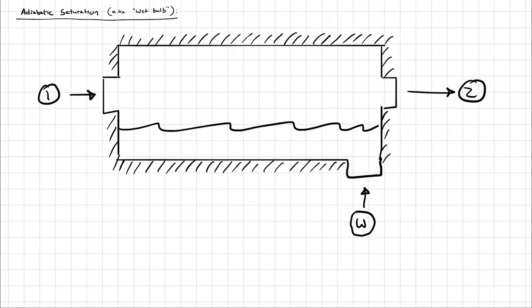One of the oldest and most accurate ways to measure humidity is with two thermometers. One thermometer measures the regular temperature. On the other thermometer, you wrap it in a wicking that holds water and allow as much water as can evaporate to evaporate. If that happens steadily, the evaporation of the water will pull some energy with it — the latent energy required to evaporate — causing the temperature reported by that thermometer to drop. You end up with a temperature difference between the regular thermometer and the thermometer wrapped in the wet wicking.